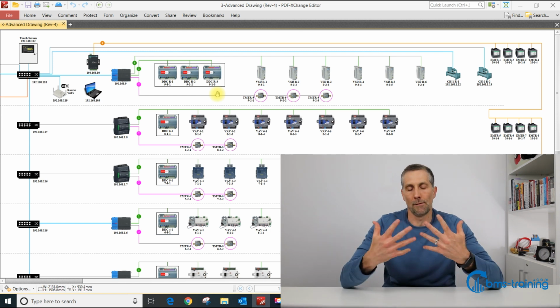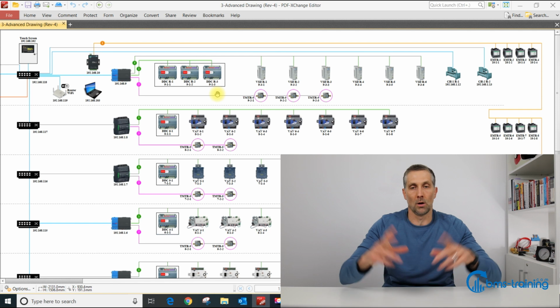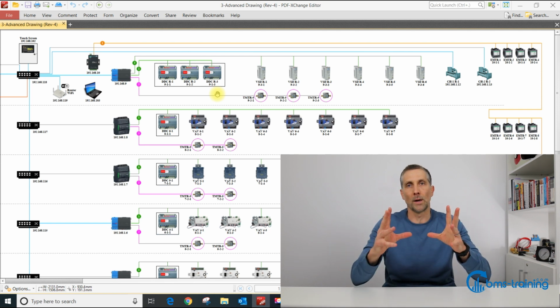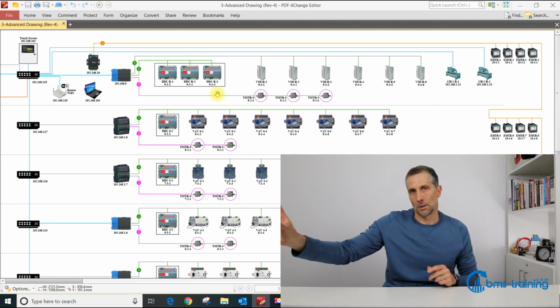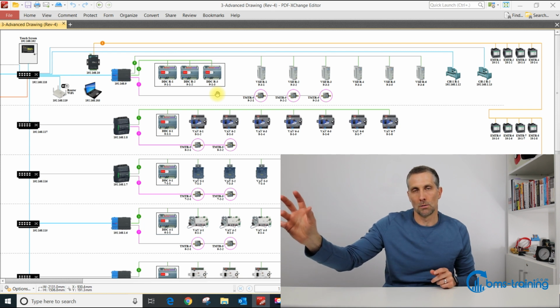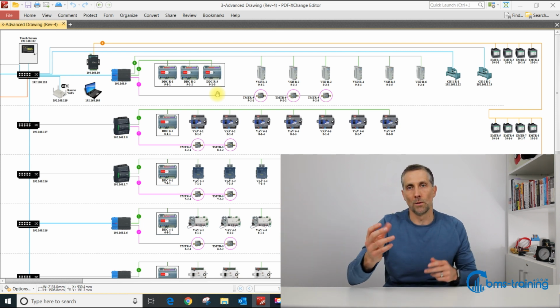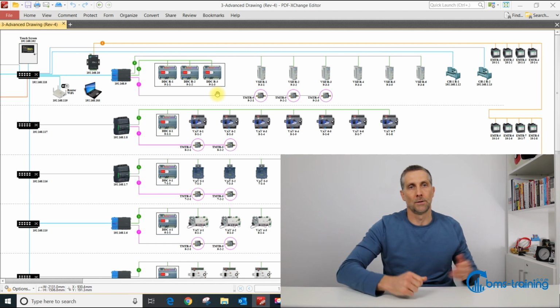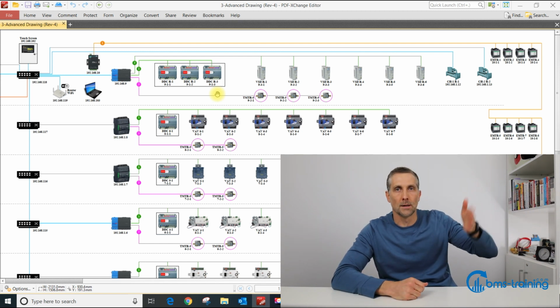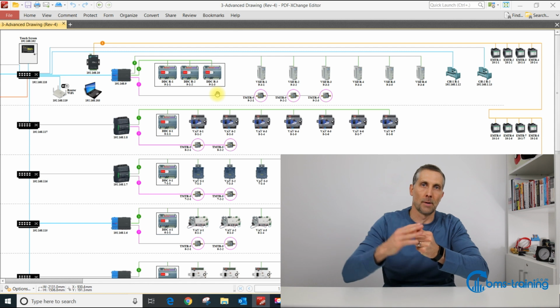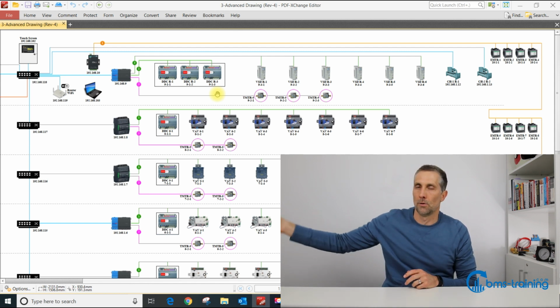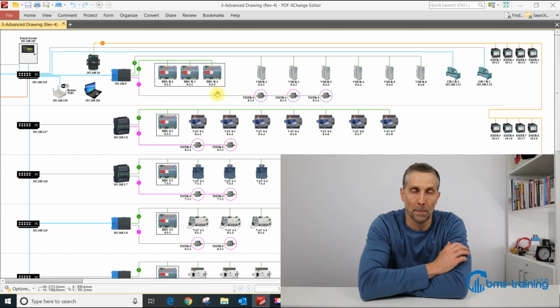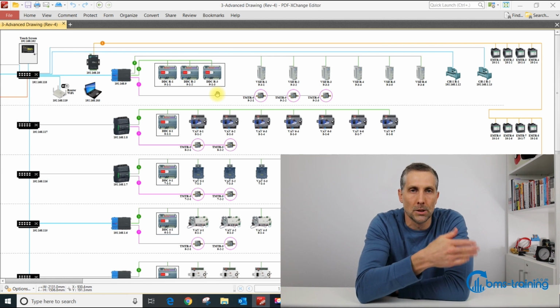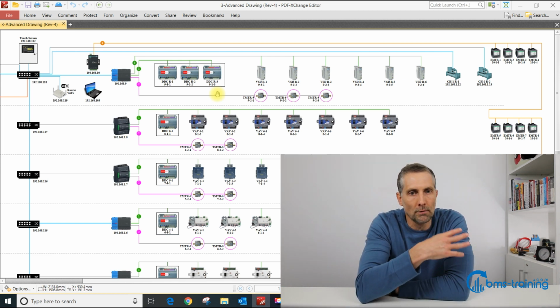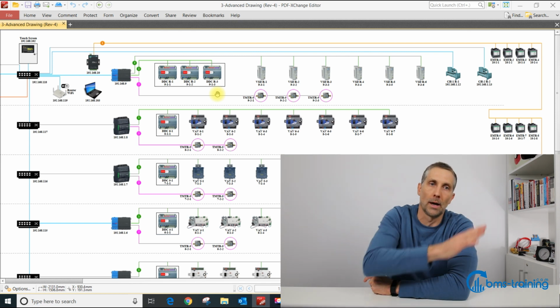So if you open up a graphic of a variable speed drive on the BMS server, and there's 5 points on there, that variable speed drive can only transmit that information back to the graphic to refresh when the VSD has the token. So if the token's coming down the run, it's got to wait, it gets the token, sends information, the token goes again. It needs to wait for the token to come back around again before it can speak again. So it's important to realize this token passing, because obviously the more devices you put down the subnetwork, the longer it takes for the token to get all the way back around.